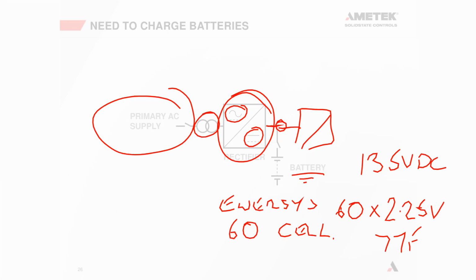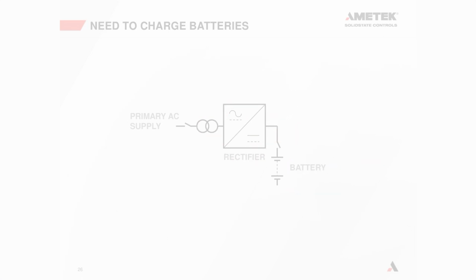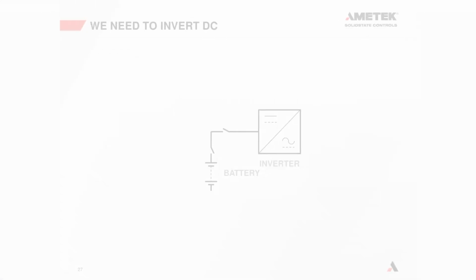Not overcharging it, which can cause it to dry out or boil off electrolyte, or if it's a valve-regulated battery, eventually dry out the electrolyte inside. Or if it was too low, it would undercharge the battery, which would cause sulfation of the plates and would eventually cause the battery to fail and wouldn't have any capacity. So it's very important we charge the battery at the correct voltage. So that is the only parameter that we care about when we're charging the batteries. That's what the charger is doing. It is there solely to charge the batteries, okay?